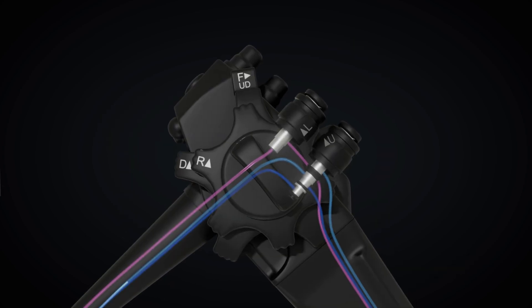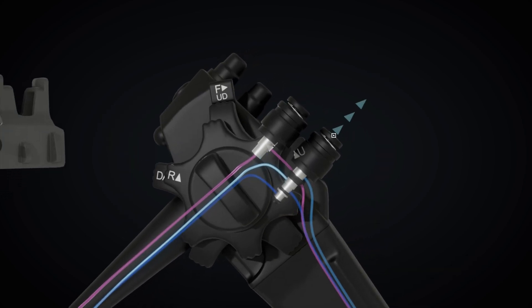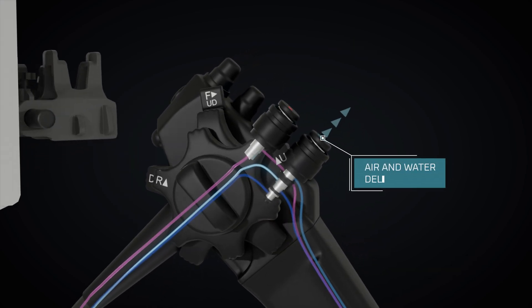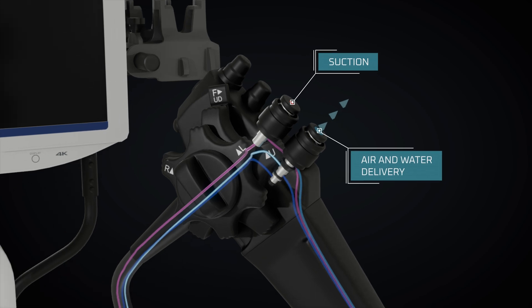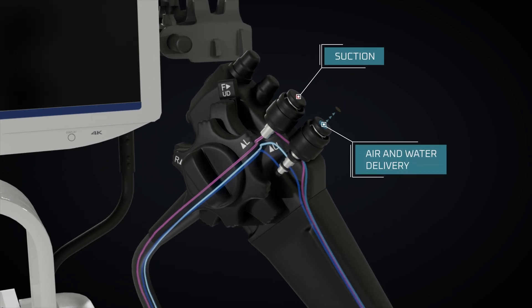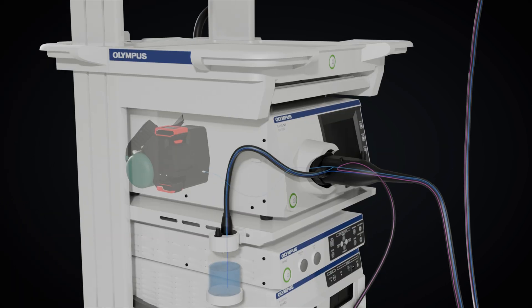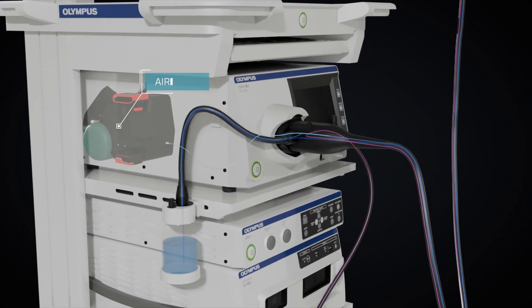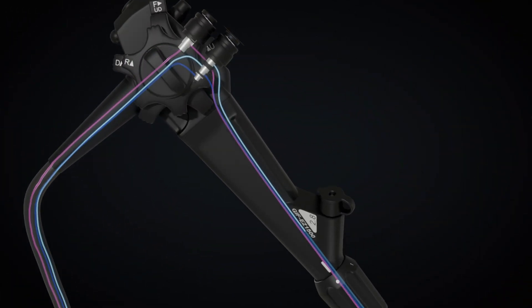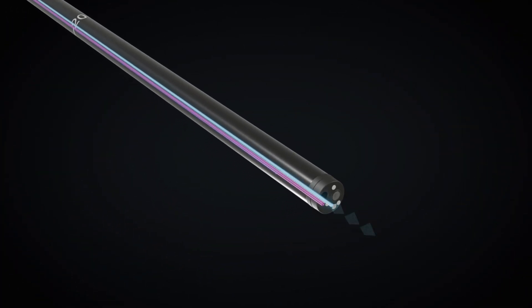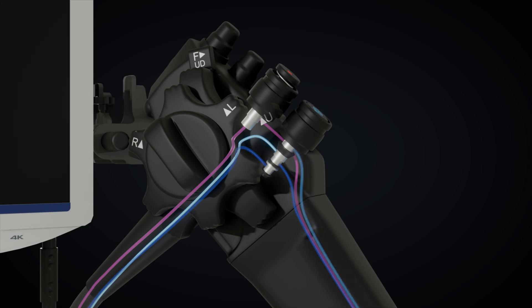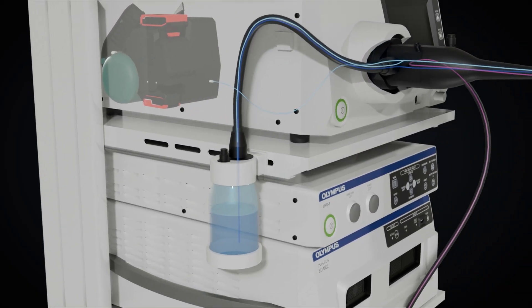Additionally, the endoscope is equipped with buttons and valves for air and water delivery as well as suction. Blocking the air-water valve aperture directs air into the observed organ, gently expanding it for better visibility, while depressing the valve allows water to cleanse the viewing lens.